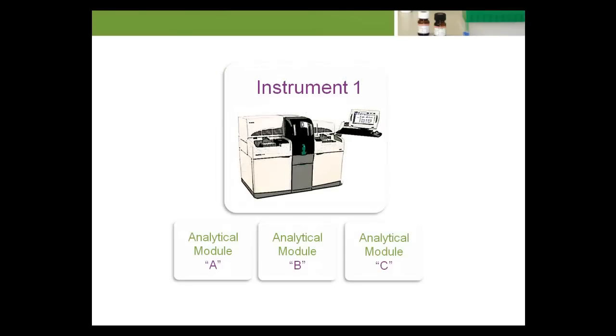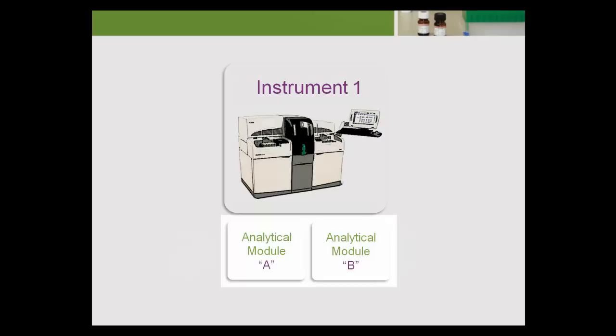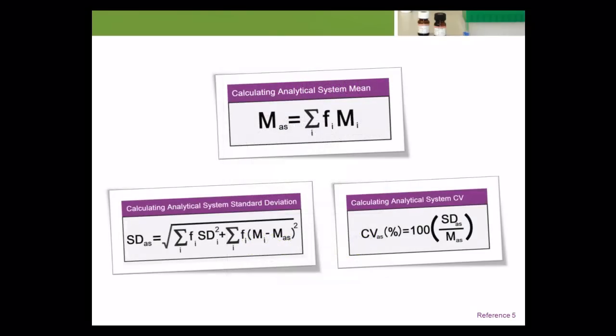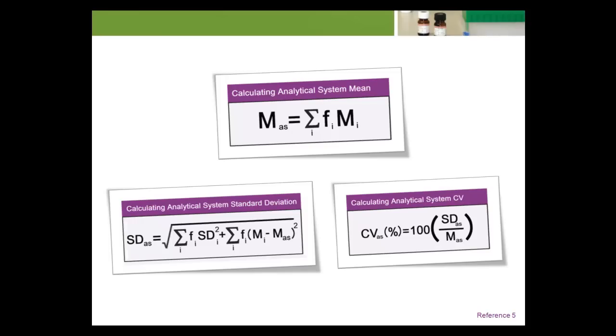Each analytical module has its own characteristic imprecision. Additionally, there may be bias between analytical modules. The total imprecision uncertainty of the analytical system will be a function of the imprecision of the individual modules and the bias between them. These are the formulas for the total uncertainty of the system.